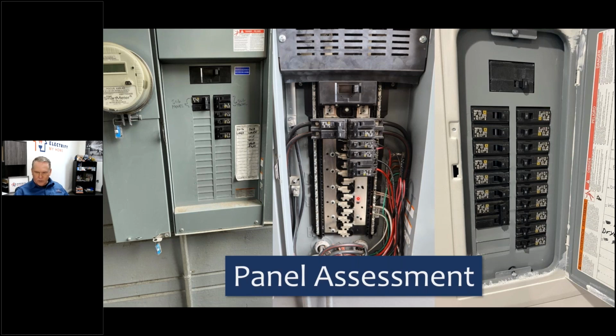The only issue came when they sized the solar system. When they put the electrical in originally, they did this 200 amp system, then added 2 100 amp sub panels, one of which existed in both spaces. But if you look at this 100 amp sub panel, it only has one 240 volt load, the dryer in each apartment, and all the others are just plug and light load. These sub panels were also installed on inside walls of the house, so you can't get any wiring into them. So this 100 amp sub panel was really a waste when it was installed, completely unnecessary, but it worked out well for us because we had plenty of capacity left in the main panel.